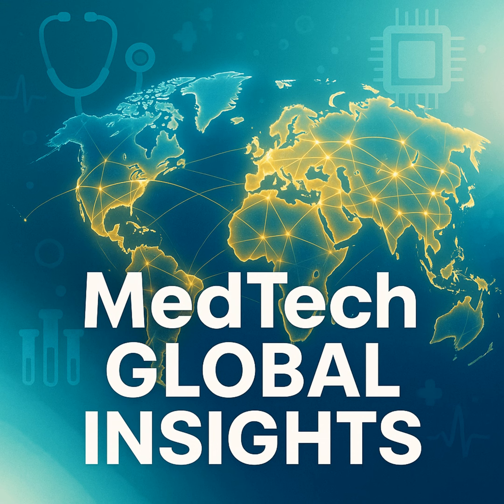For high-risk Class 3 devices, such as life-supporting implants or novel diagnostic systems for critical diseases, the pathway is Premarket Approval, or PMA. This is the most stringent and expensive route. Unlike a 510(k), a PMA requires you to prove your device is safe and effective on its own merits, which demands extensive laboratory and clinical trial data. A classic mistake is underestimating the sheer volume and quality of clinical evidence required.